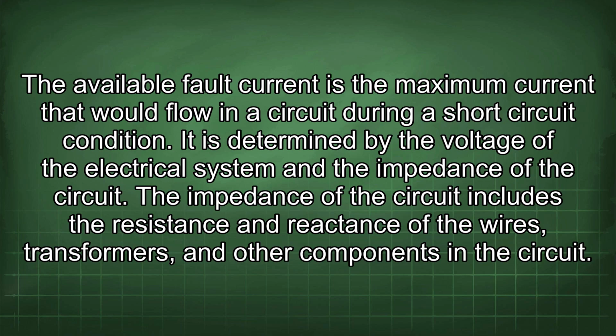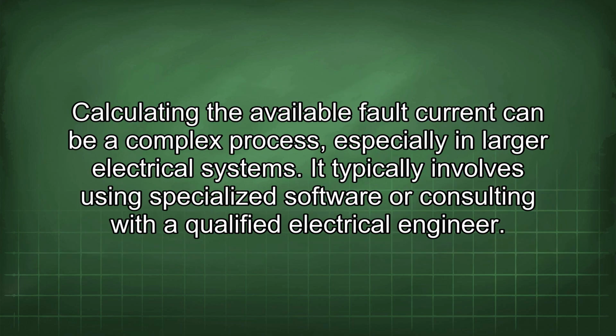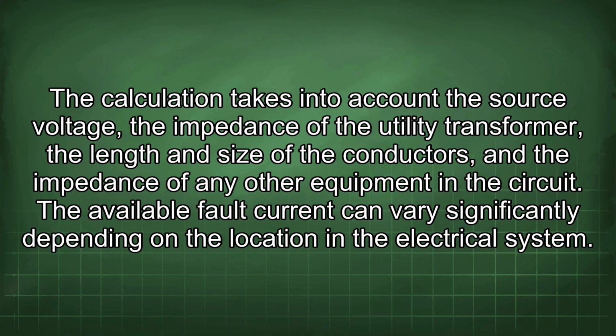The impedance of the circuit includes the resistance and reactance of the wires, transformers, and other components in the circuit. Calculating the available fault current can be a complex process, especially in larger electrical systems. It typically involves using specialized software or consulting with a qualified electrical engineer. The calculation takes into account the source voltage, the impedance of the utility transformer, the length and size of the conductors, and the impedance of any other equipment in the circuit.